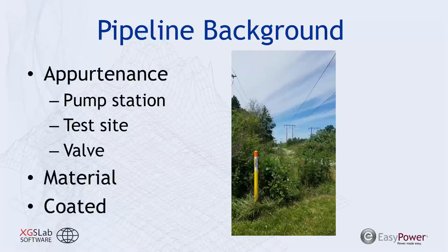Another thing to note is what material that pipeline is made of. If you're looking at it, it's going to be a metallic pipeline, probably steel, and it usually has some sort of coating around that steel to reduce the corrosion of that buried pipe. But that coating is acting as an insulator from the earth. It also allows for higher voltages to be induced upon that pipeline from a parallel transmission line. So you can end up with higher voltages when you have a very good pipeline coating.